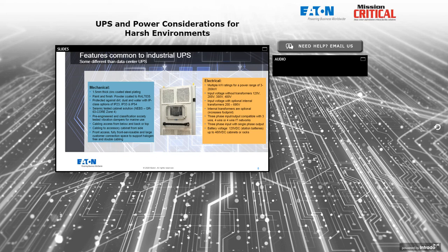And then battery voltages anywhere from less than 120 volts DC to beyond 480 volts DC, both in cabinets or racks. The 120 volt DC requirement is very common because it matches the typical voltage that you might see in a station battery in a factory or a manufacturing environment, and the client is going to want to use that large battery that he's made a big investment in to power the UPS.